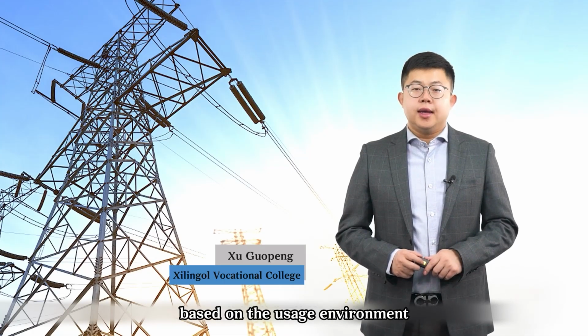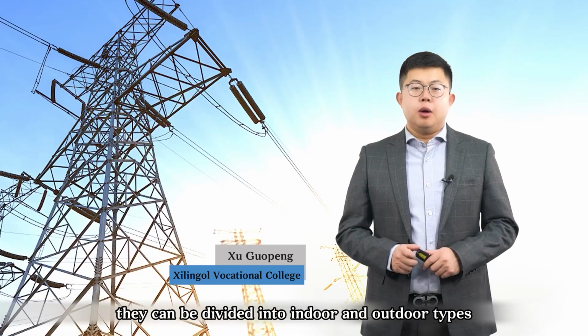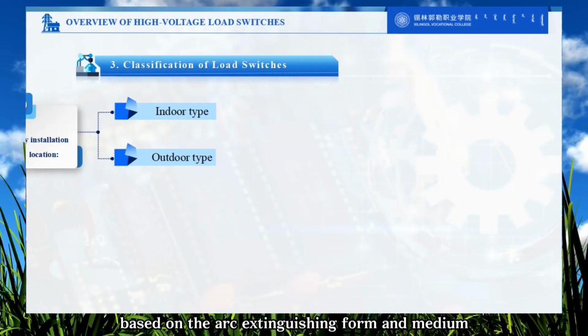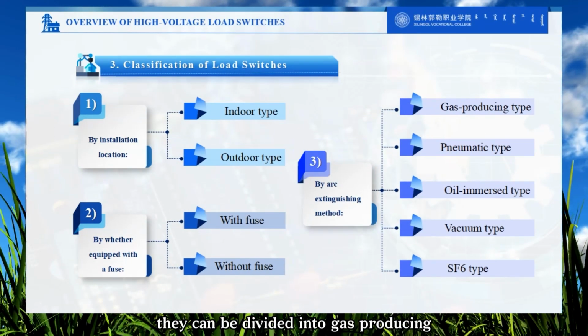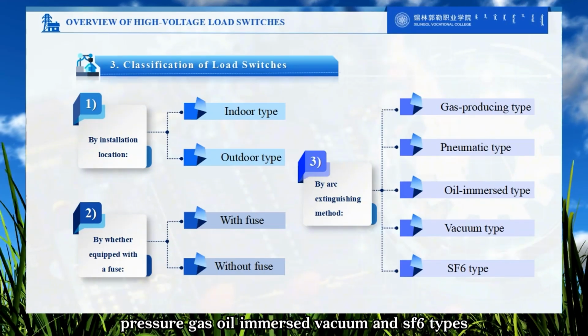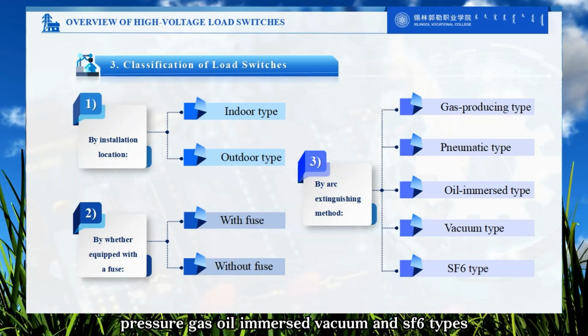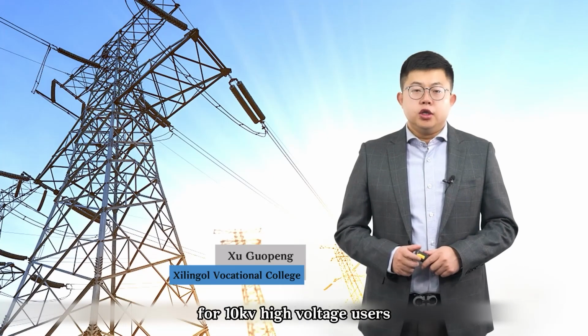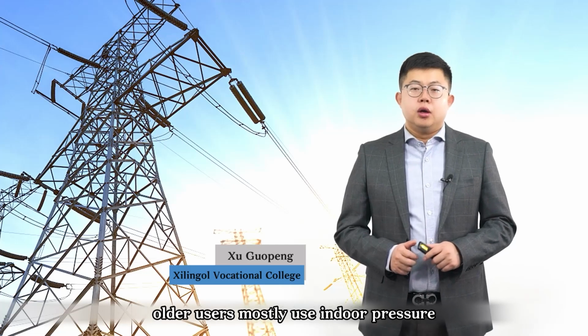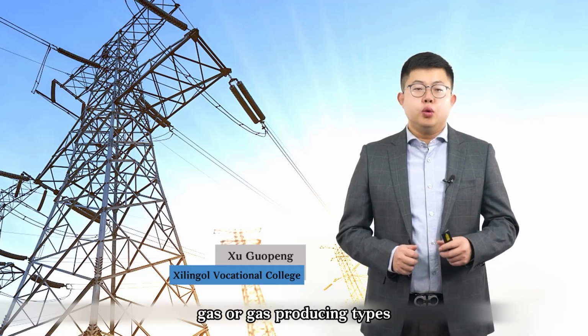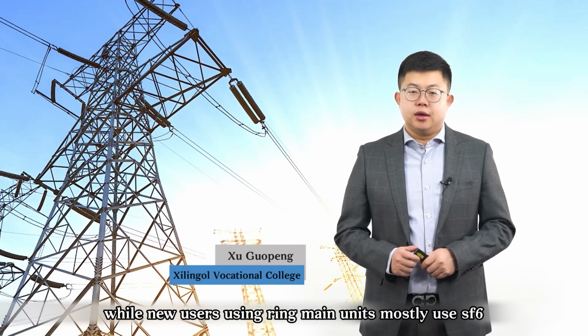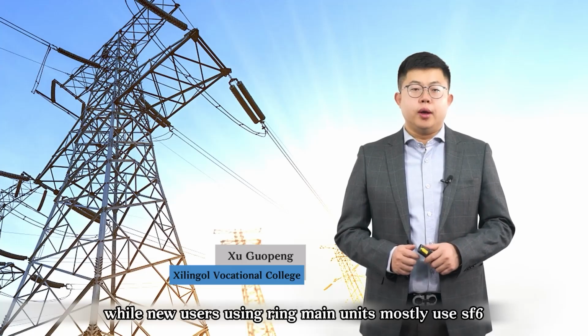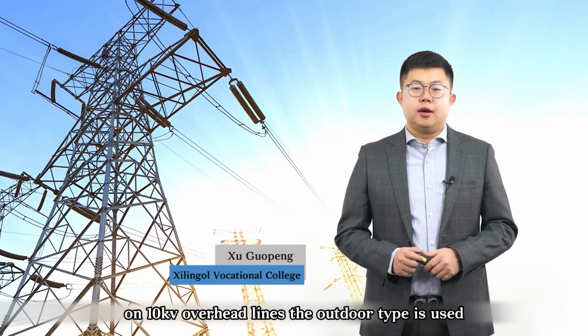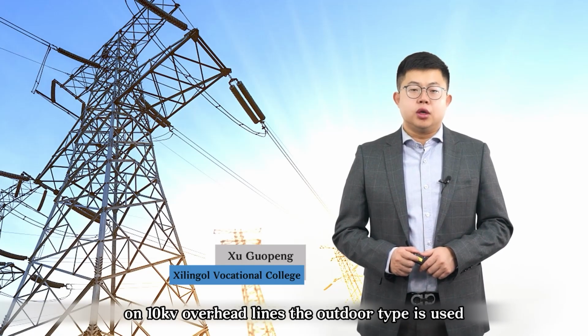Based on the usage environment, they can be divided into indoor and outdoor types. Based on the arc extinguishing form and medium, they can be divided into gas-producing, pressure gas, oil-immersed, vacuum, and SF6 types. For 10 kV high-voltage users, older users mostly use indoor pressure gas or gas-producing types, while new users using ring main units mostly use SF6 types. On 10 kV overhead lines, the outdoor type is used.